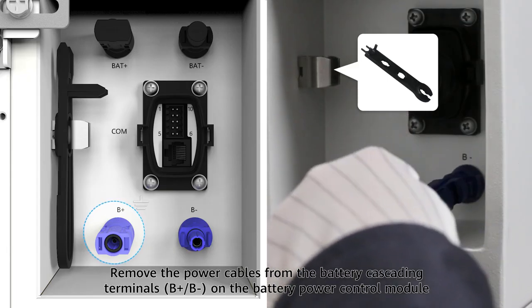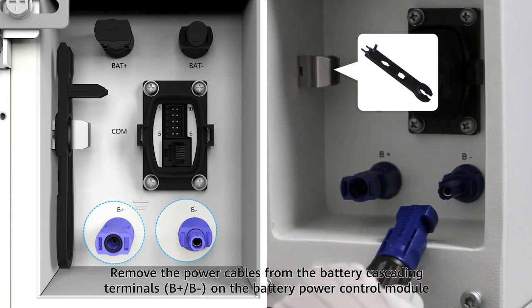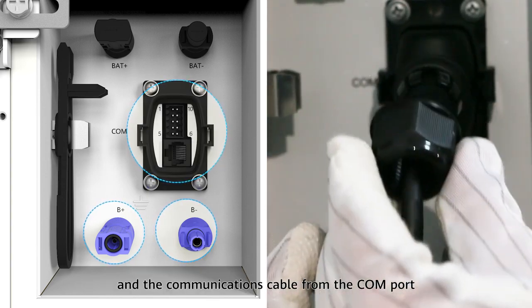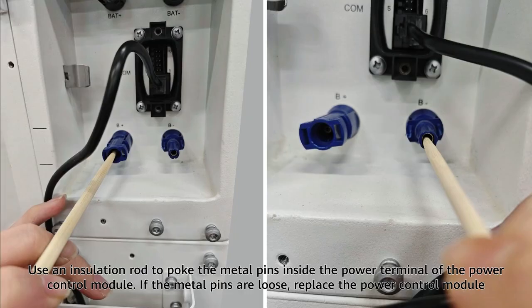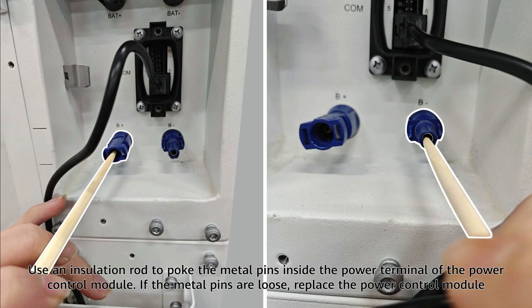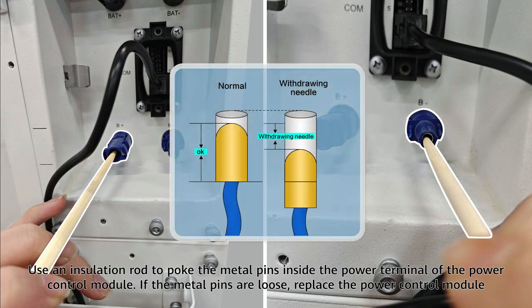Remove the power cables from the battery cascading terminals on the battery power control module, and the communications cable from the COM port. Use an insulation rod to poke the metal pins inside the power terminal of the power control module. If the metal pins are loose, replace the power control module.